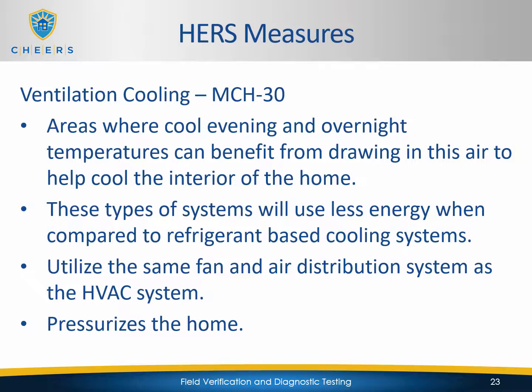So in areas where cool evening and overnight temperatures can benefit from drawing in this air to help cool the interior of the home, these types of systems will use less energy when compared to refrigerant-based cooling systems. They will utilize the same fan and air distribution system as the HVAC system, and it will pressurize the home. So a ventilation cooling system is essentially an additional return duct that is ducted to the outside. It's going to draw outdoor air into the HVAC system. The AC part of that system is not going to run. All you're going to do is turn the fan on. It's going to suck the nice, cool air from outside, bring it in through the distribution ducts and into the home.